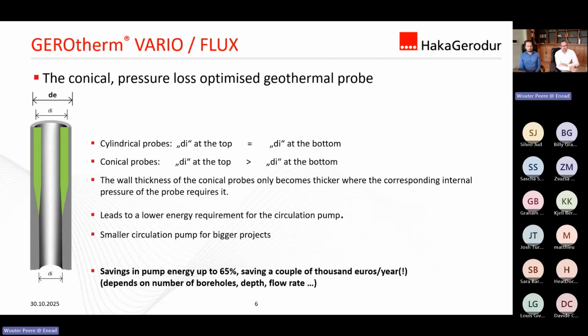So what does that bring? The media, the brine or the water, has less restriction in the upper part of the probe, so you have reduced pressure drop. So the brine has less restriction and your circulation pump doesn't need as much power to push the fluid through. So that's the whole magic. And for bigger projects, you can also size the circulation pump smaller. So you have energy savings of, depending on the project, up to 65%. And for a bigger project, you save thousands of euros every year. For the drillers, that might not be that interesting because they just like to drill a borehole, put the probe in, grout and leave. But for the operator or for the designer, this is a very interesting product.